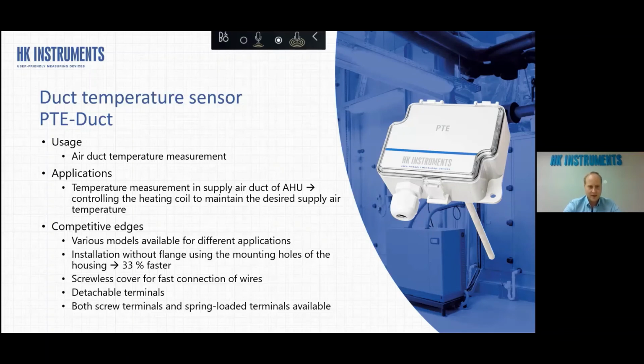And we have this one for five or six different sensor elements like NTC 10K, 20K, PT1000, nickel 1000, and this nickel 1000 for Siemens logic. And this duct sensor you can install straight away to the duct. In some cases, you don't need to have the flange, which is sometimes a bit problematic to install because, as you can see from the picture, you have these ears which have the screw holes, so you can screw it directly to the duct. And we have also these detachable terminals for easier commissioning for the wires.